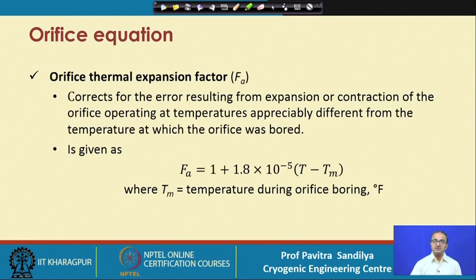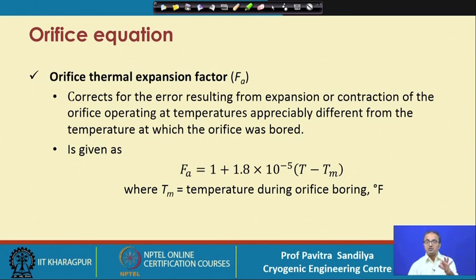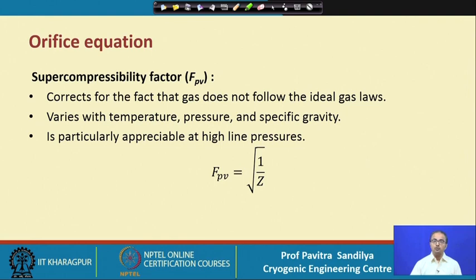The thermal expansion factor FA corrects for any expansion or contraction of the orifice due to temperature change — if temperature is very high the orifice itself expands, and if low it contracts. This contraction and expansion with gas temperature is corrected by the formula FA, which has been given empirically. The super compressibility factor — the compressibility factor — accounts for changes in pressure, temperature, and specific gravity.